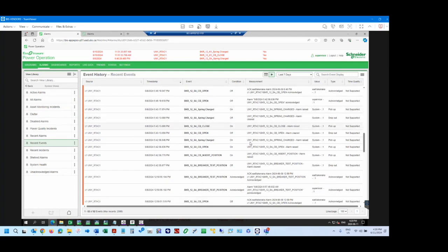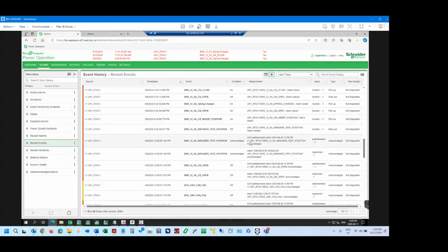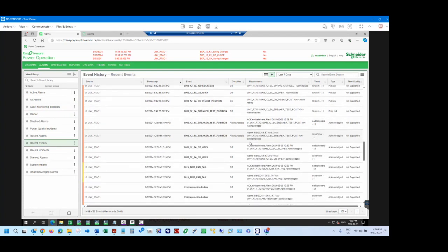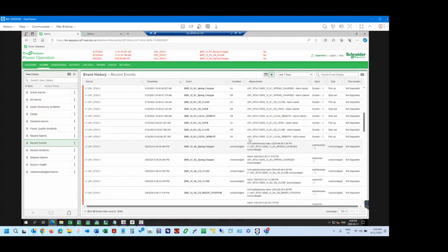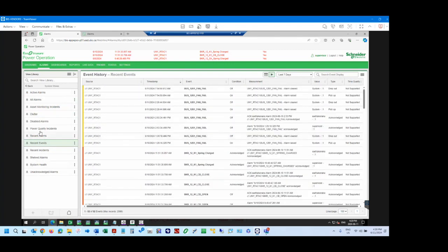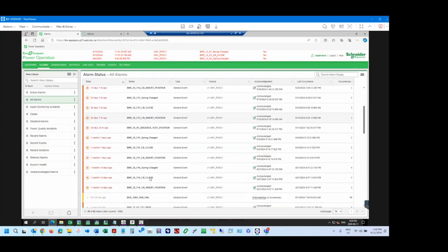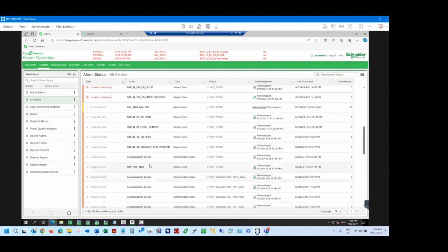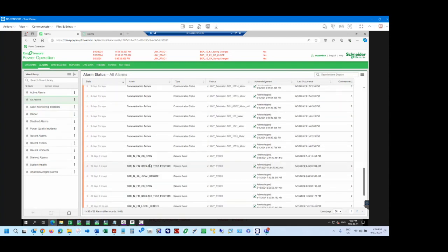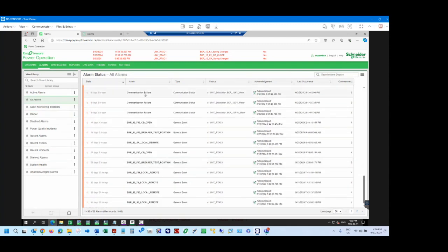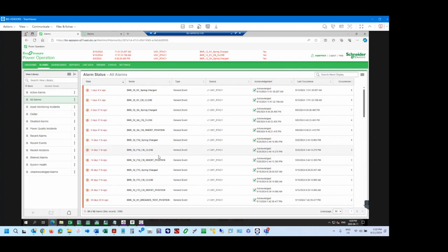Is there any correlation to this and the power quality event? Do they show up on here? Yeah, like disturbances, they will. They will come in here, yes. Because presumably, if we had a breaker trip, it would have triggered a disturbance. Yeah, let me find an example. We did have one that happened in February. I'm not sure how far back you can go on here.